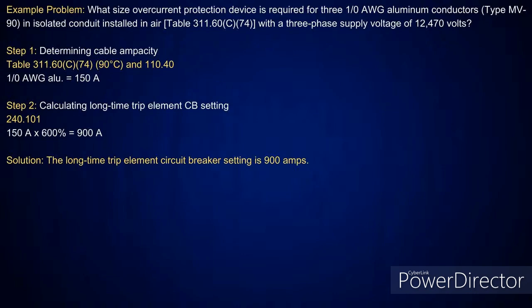And then you go over there and you pick up your amperage for a 1/0 aluminum, and it's going to tell you it's good for 150 amps. And then when you go over and look at your long time trip element circuit breaker rating in 240.101, it's going to tell you to take it at 600%, which will give you a circuit breaker setting of 900 amps.